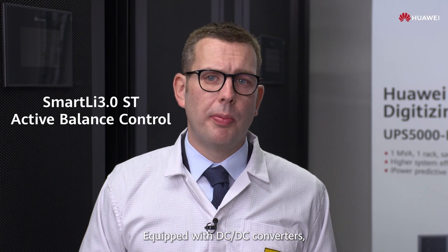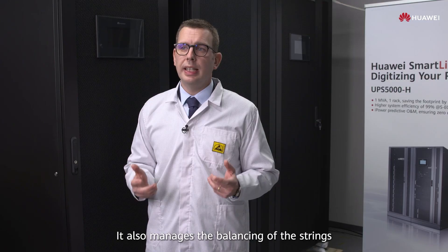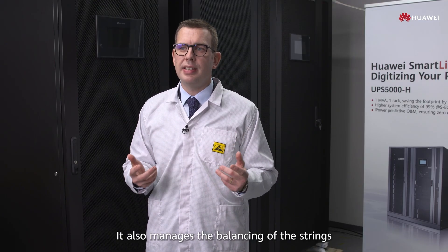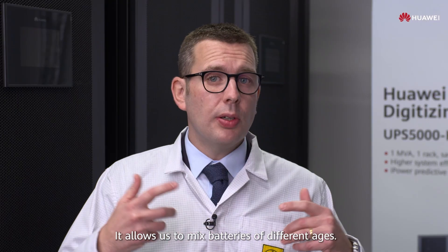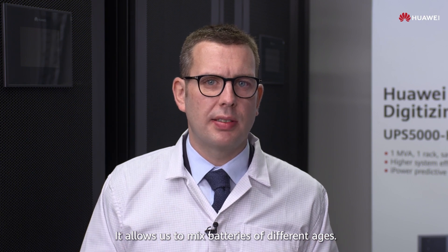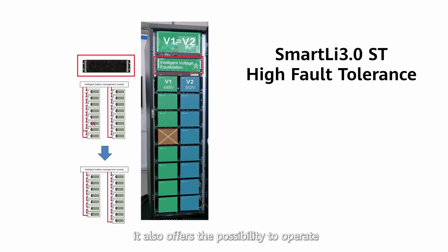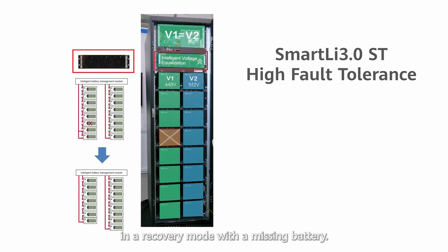Equipped with DC-DC converters, the BCU is not only a monitoring device. It also manages the balancing of the strings during a discharge phase. It allows us to mix batteries of different ages. In addition, it also offers the possibility to operate in a recovery mode with a missing battery.